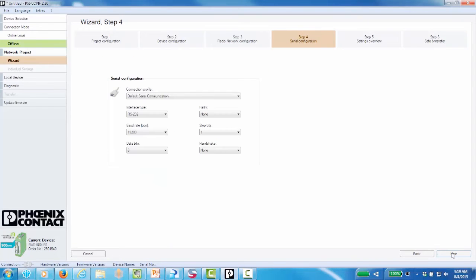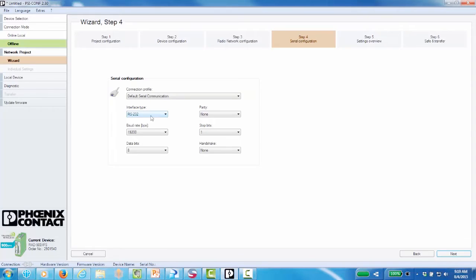Next configure the settings for the serial connection between the host device and the master wireless module. This will vary from application to application. Set to RS-485, 9600, 8-N-1. Click Next.